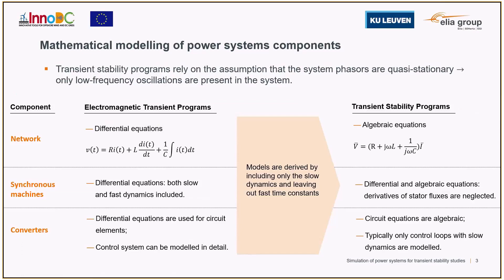Considering how power system components are modeled mathematically, the main difference is that EMTP does not necessarily make any assumptions on the component models, while models using transient stability programs are based on what is called the quasi-stationary phasor assumption. This assumption is based on the fact that only low frequency dynamics are taken into account, leaving out higher frequency dynamics associated with smaller time constants.